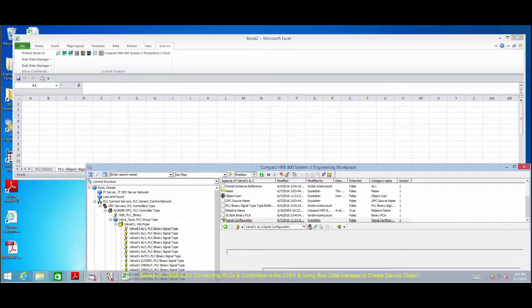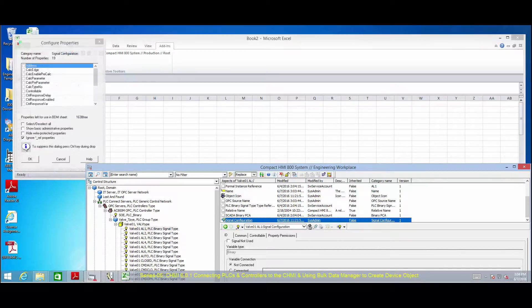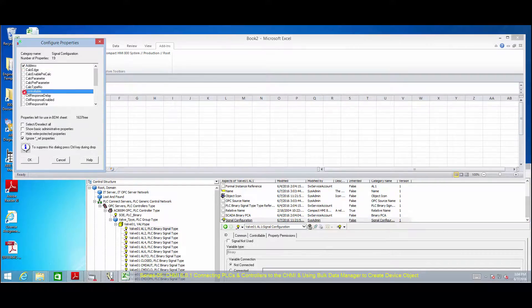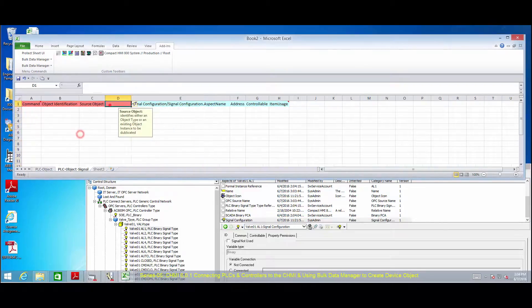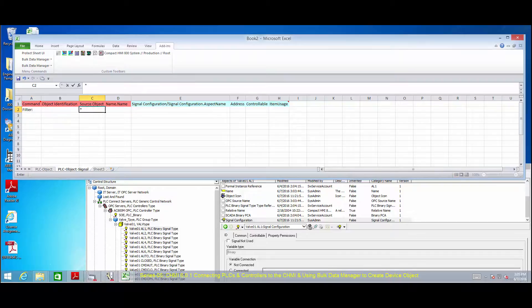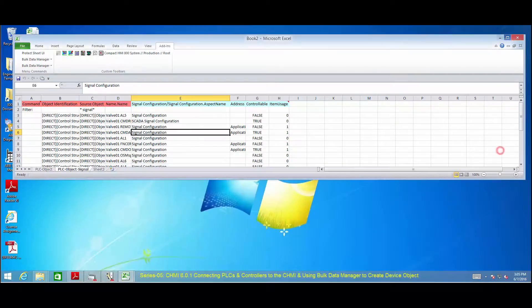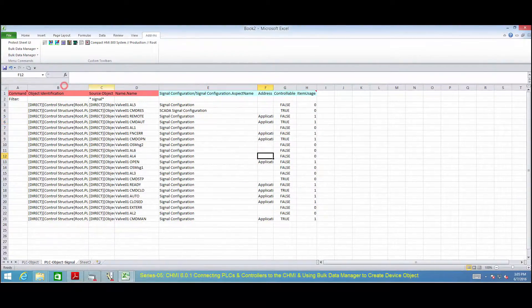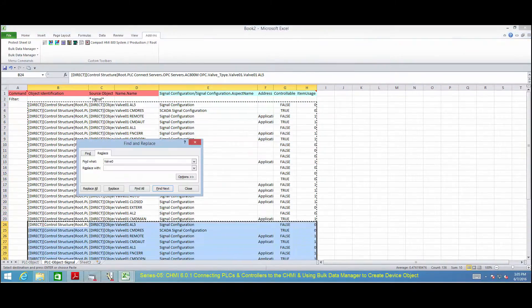To create the signal configuration, select any of the Valve 01 device object binary signal type and select the signal configuration aspect. Drag and drop the aspect to the second sheet in Excel and configure the desired properties using the configure property window as shown. Users have the option to use the filter function to customize the view of the source object. Copy and paste the signal and use the Excel replace feature to replace Valve 01 with Valve 02, and save the bulk data manager as shown.